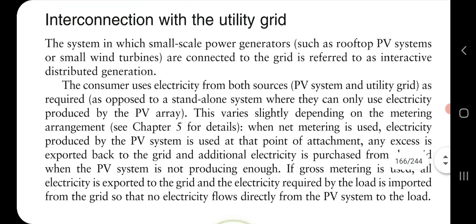Now next, the interconnection with the utility grid. A small-scale power generation system connected to the grid is referred to as an interactive generating system. The consumer uses electricity from both sources: from the PV system and from the utility grid, depending upon the requirement. The metering changes a little bit here. When net metering is used, electricity produced by the PV system is used at that point of attachment. Any excess is exported back to the grid, and any additional electricity required is purchased from the grid.